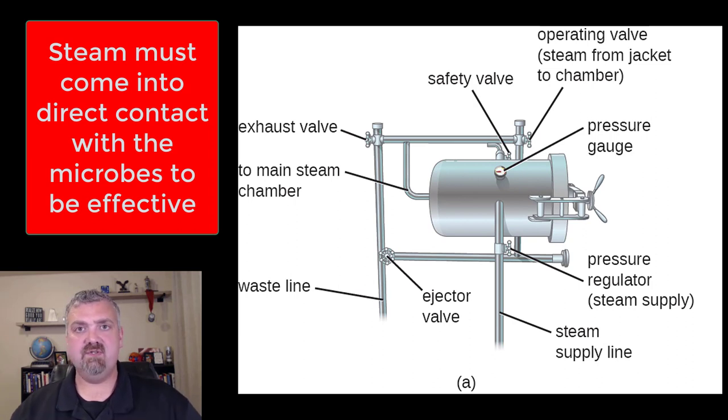So you can't have sealed containers. You don't want air pockets forming in any of your containers. That is like the biggest weakness of an autoclave. The steam must come into direct contact.